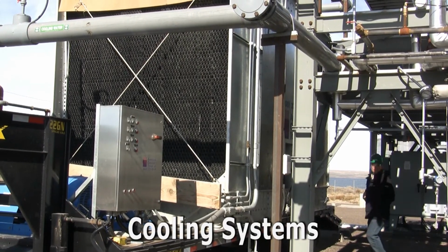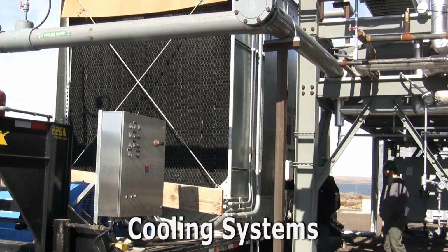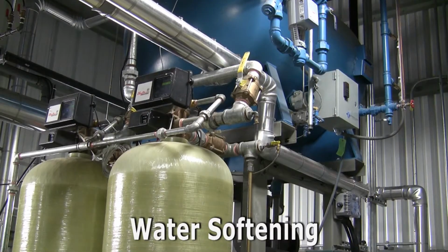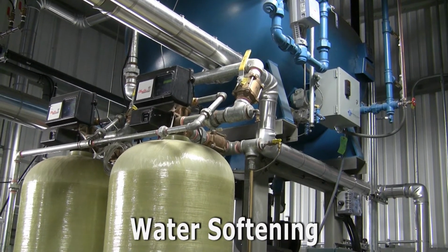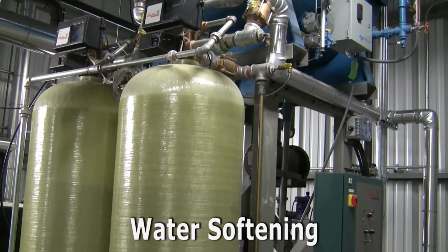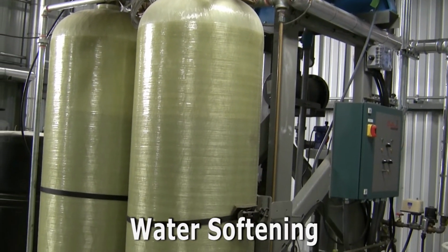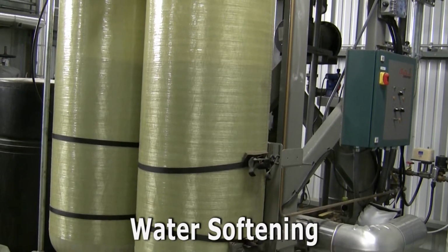You have to maintain the chemistry of the cooling tower. You've got to make sure the pH is right, and you need to know you're not putting hardness into your boiler. This is pretty basic to operating a boiler system.